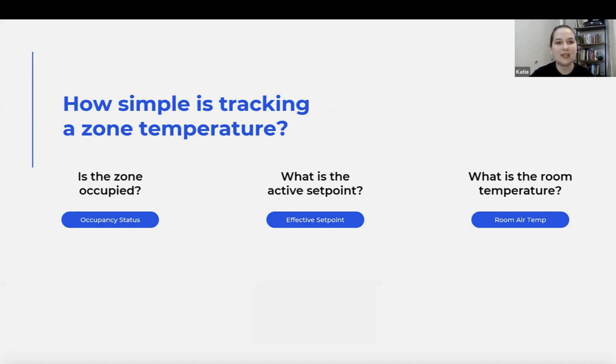So when you are looking at a fault for a zone being above or below set point, the reason this is a nice fault to have is when you're looking at a campus environment, you all know this, you have thousands of zones everywhere, and being able to track whether they're all in compliance is a very difficult task. You're really, for the most part, waiting for a comfort call. You're waiting for the occupant to be uncomfortable enough that they will call into your work control center. And so this is a nice fault to have because you can see, oh, I know all of the zones that are out of compliance on my campus. I know how far they might be out of compliance, and I can go hit the big hitters.